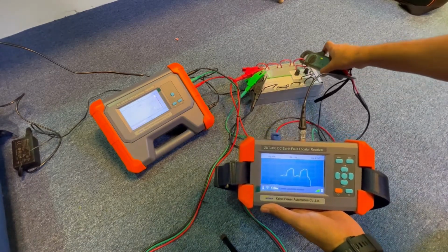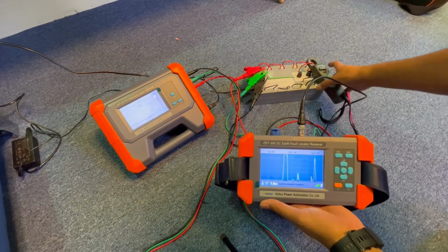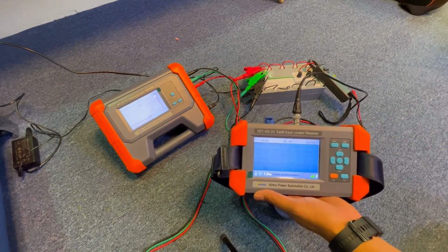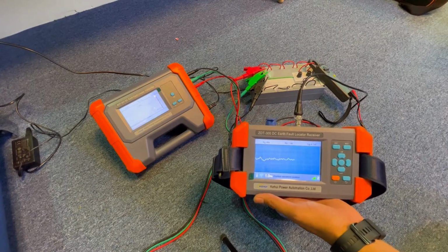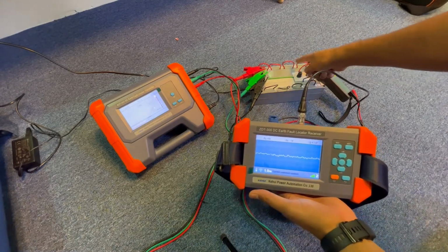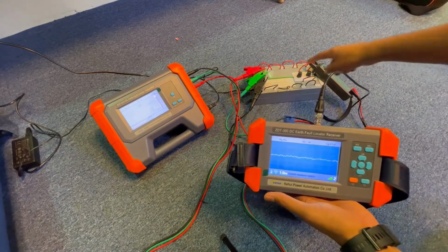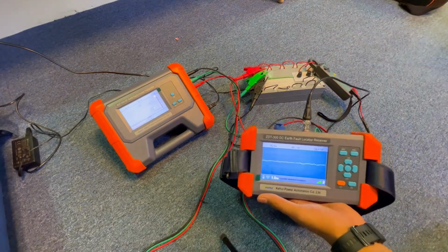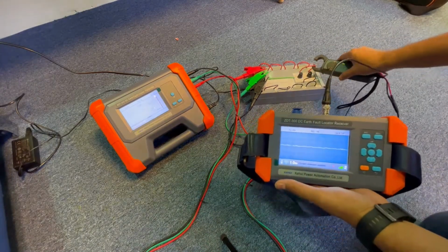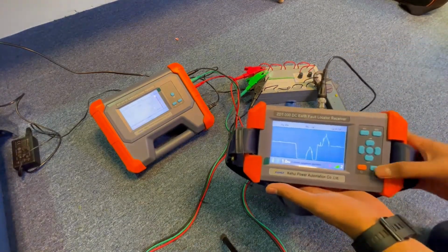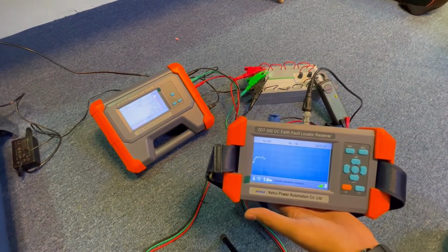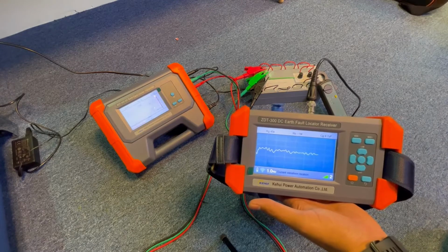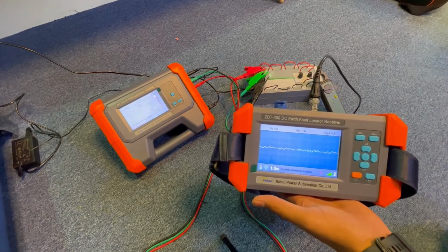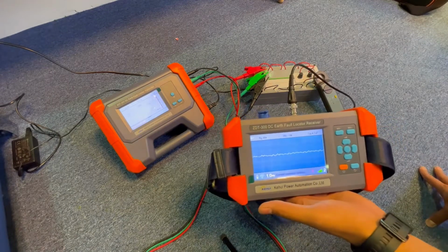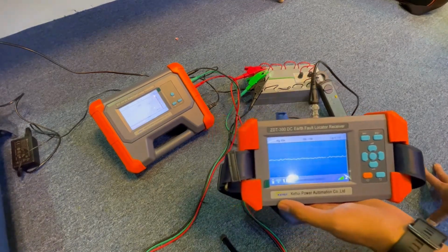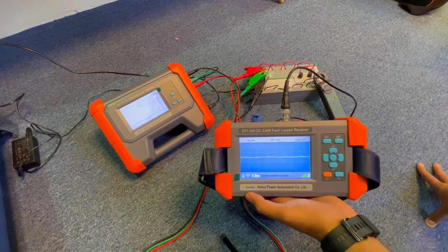So next we go to the next feeder and then we refresh. There's no signal, which means the fault is still at this point. The fault is not going to the other point. So you are exactly knowing where the fault ends. So this is how you can do it. Let's go to the negative feeders and check. Since there is no negative fault, there should be no signal in the negative. So just a straight line. So there is no fault in the negative. This system is very accurate and helps you to exactly pinpoint which feeder is faulty, and it will trace you till the fault point.